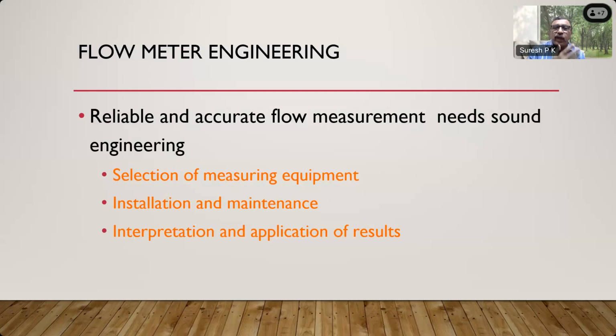But you have to see your own condition also. If you have a zigzag pipeline upstream of the flow meter and you give only 20D, it may not be sufficient. Your idea is to give a steady flow with a proper velocity into the flow meter so that it can measure accurately. If you give a flow which is pulsating, swirling, or with multiple phases, with air coming in between, then you cannot blame the flow meter for not measuring properly. The flow meter can measure properly only if you give it a proper fluid flow. Then only can it perform to its specified accuracies. Otherwise, you just cannot blame the flow meter.